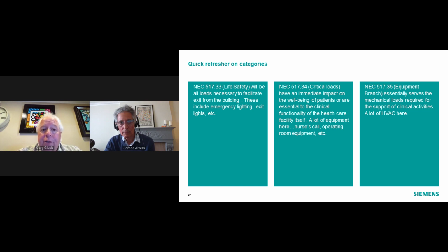Okay, so just a quick refresher on the categories. 517.33 is life safety. This is pretty analogous to Article 700, because it's going to facilitate all the loads that are necessary to exit the building during an emergency. That will consist of emergency lighting, exit lights, etc. 517.34 is critical, and those are loads that have an immediate impact on the well-being of patients or are essential to the clinical functionality of the healthcare facility itself. So we have a lot of equipment here: nurse call stations, operating room equipment, etc.